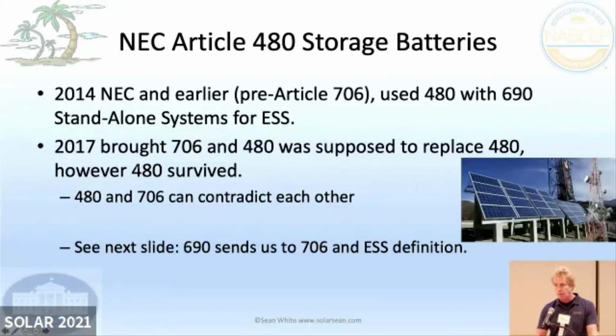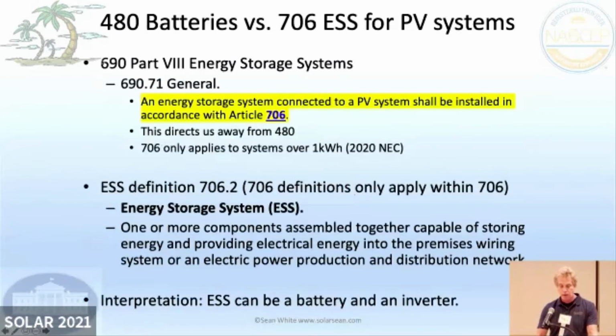2017 NEC, we made a lot of changes. In Article 690, if we're doing a PV system with batteries, energy storage, do we use 706 or 480? So in 690, it says an energy storage system connected to a PV system shall be installed in accordance with 706. So that directs us away from 480. Another thing, though, is 706 only applies to systems over 1 kilowatt hour. Most energy storage systems are over 1 kilowatt hour. You could maybe make one that's just a little bit less and trick the code, find a loophole or something.